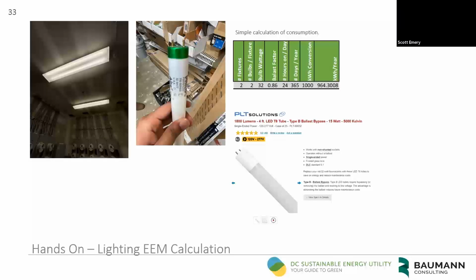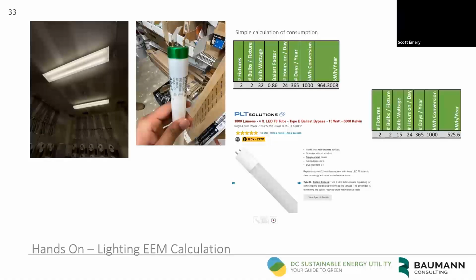So here's your efficient EEM. We're going to replace them with a 15-watt bulb, but you have to bypass the ballast. So here's your proposed case. It's going to be 2 fixtures, 2 bulbs, 15 watts this time, 24 hours a day, 365 days a year, then your conversion factor, and then you only have 525 kilowatt hours per year. It's a simple calculation. You're going to end up saving 439, which is almost half of the consumption from the conversion.